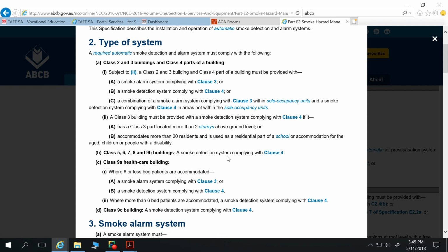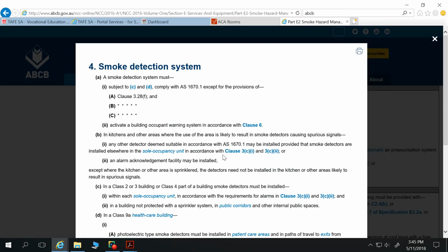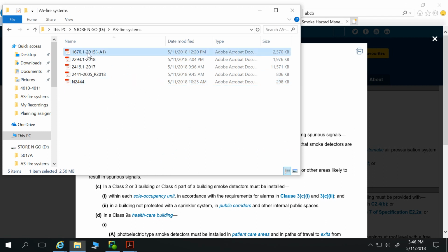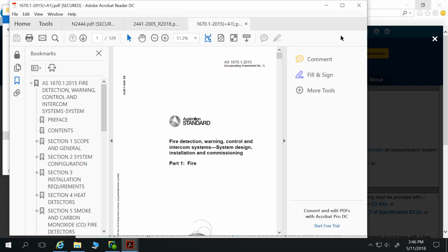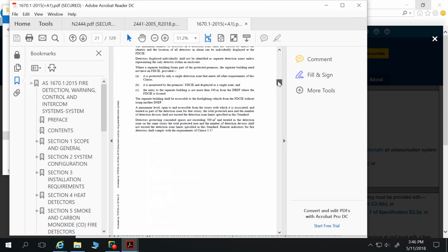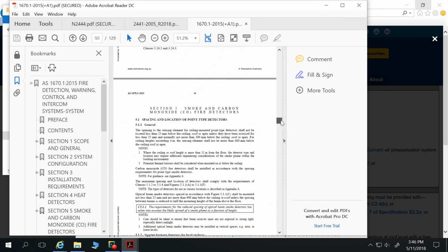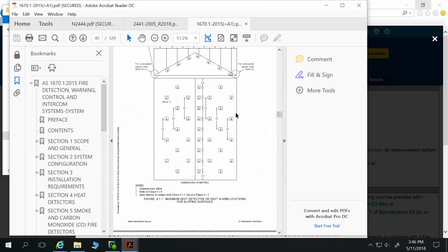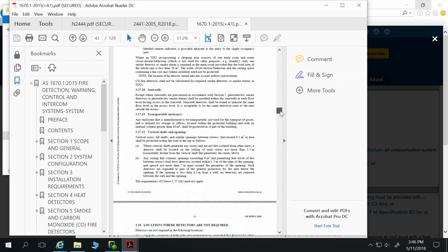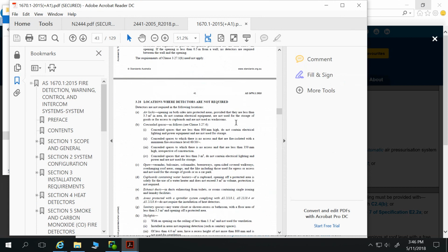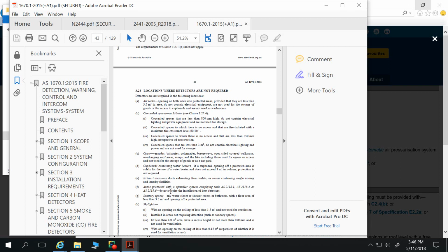So smoke detection system complying with clause 4. Smoke detection system must, subject to C and D, comply with AS 1670.1, except for the provisions of clause 3.28F. So we can quickly look at 1670.1 and, what was that, 3.28F, was it? Areas protected with the sprinkler system complying with. Okay.